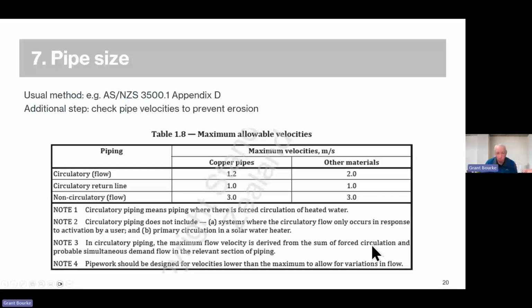So once we've done our pipe sizing, we just need to go through and check that we're not above these velocity limits, not volumetric limits, but velocity limits for the pipes. In the book, I've converted these velocity limits into litres a minute for common pipe sizes to make it a bit easier. So a couple of notes here. It doesn't include where flow occurs only in response to activation by a user. Now, that's not that common in New Zealand.